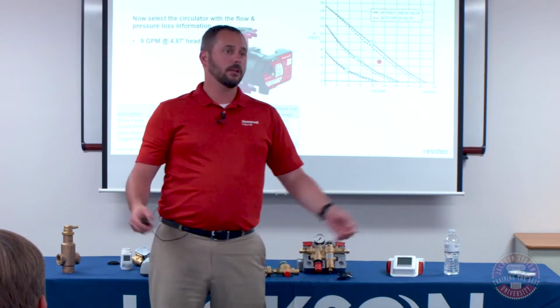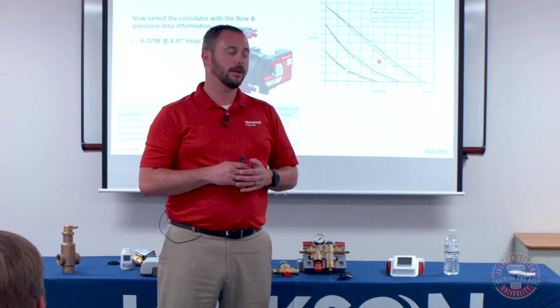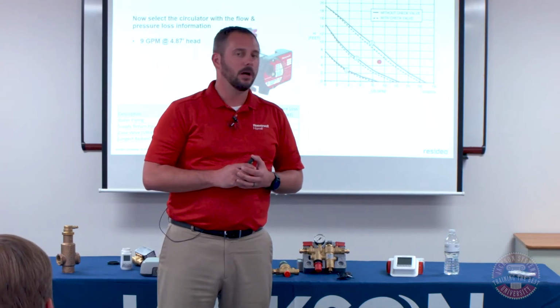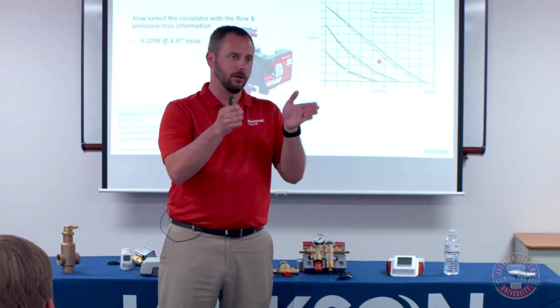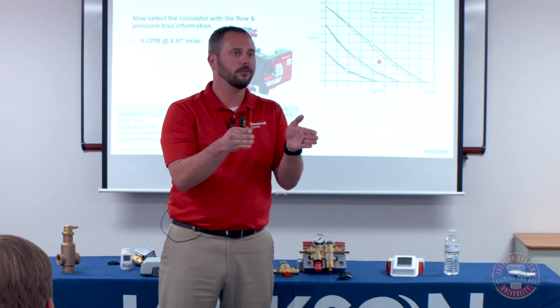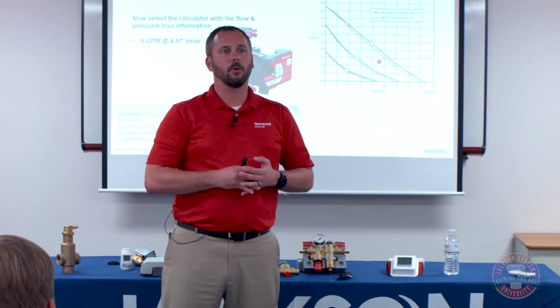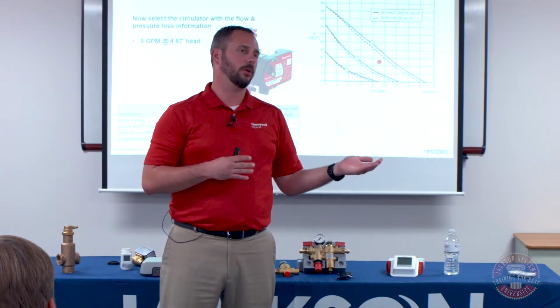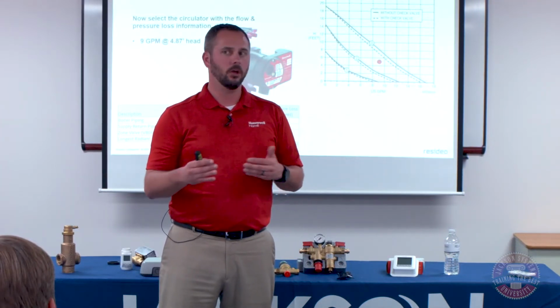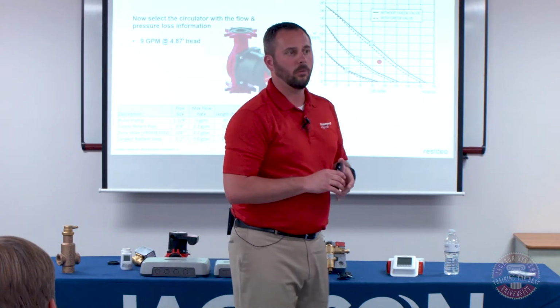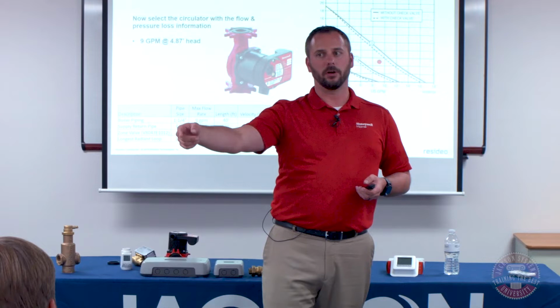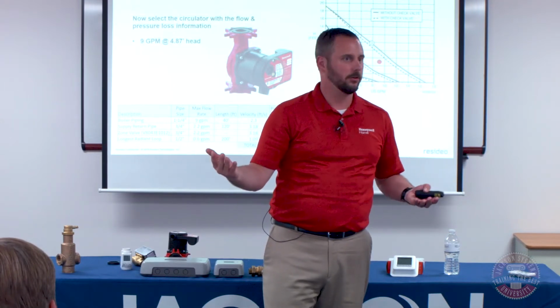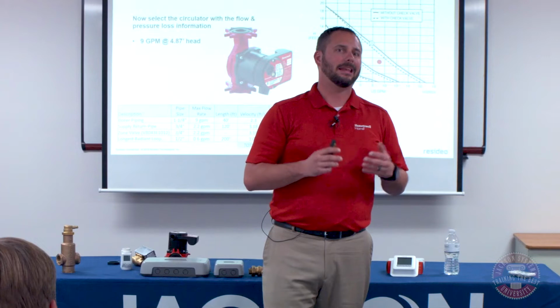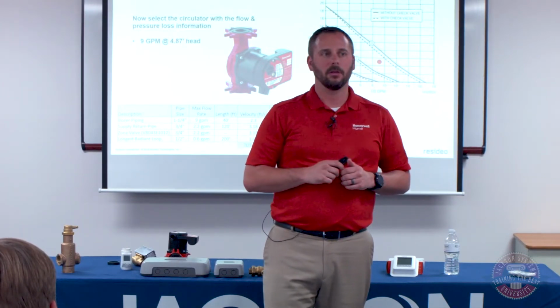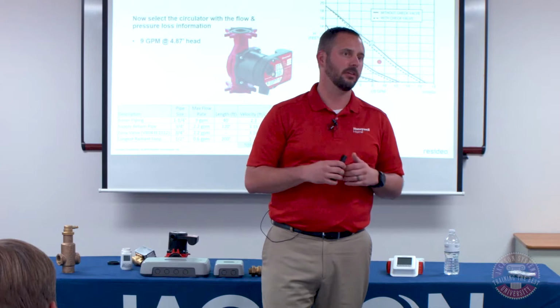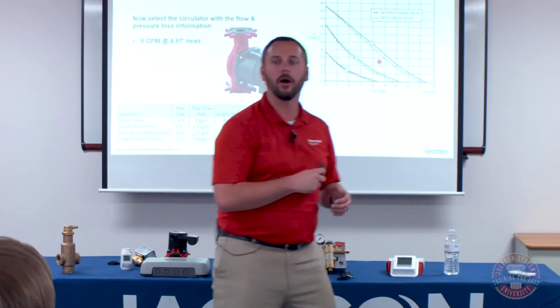Good question. If you don't make the right selection on the pump on 1, 2, and 3, you go to a bigger pump. Most of the pumps in that residential line are going to match up to pretty much the same bolt dimension, so you just slap a bigger pump in there. But realistically, what happens is if you're a little bit off, say we sized that for a 20-degree delta T, you won't get a 20-degree temperature differential. Maybe you're going to get a 23-degree temperature differential. It's pretty minuscule, and 99.9% of the time, the numbers you're running are overstated anyways. So there's a lot of cushion built into everything when you're doing that as well. Great question, though.